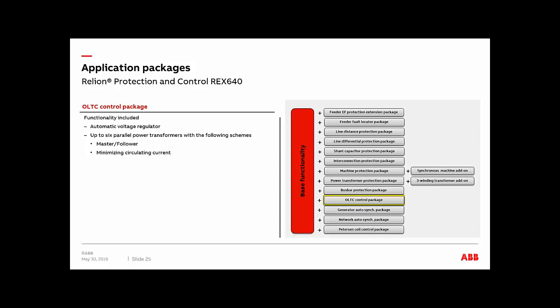We do have an on-load tap changer, I'm sorry, excuse me, and it also comes with an automatic voltage regulator. Now you do have the option of paralleling up to 6 transformers, and there's 3 schemes that you can have. There's a master follower scheme, which needs 2 identical transformers as far as impedance and number of taps and tap steps as well.